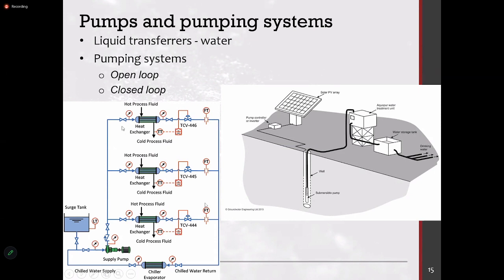But nowadays what we do is we don't bypass, we use a valve here and shut the water flow here. So once you shut the water flow, the pressure at the outlet of the pump will start rising, because now the system is smaller.